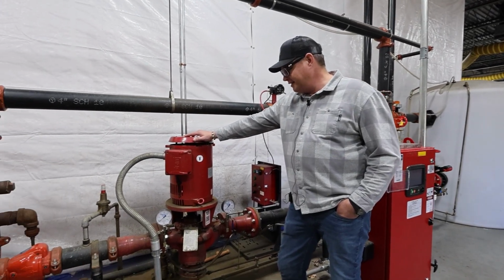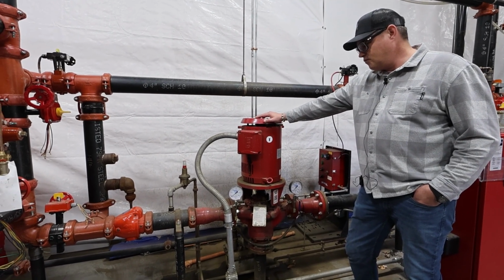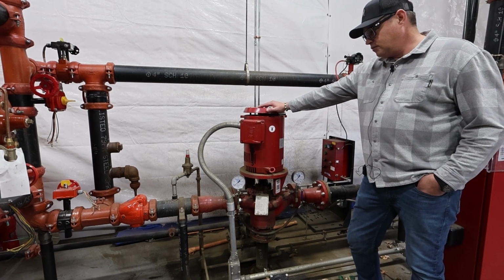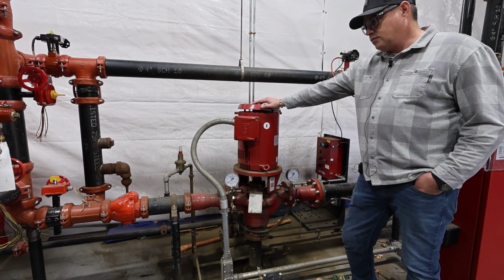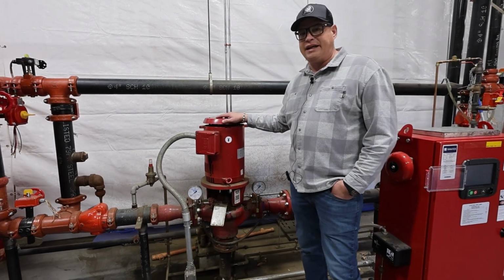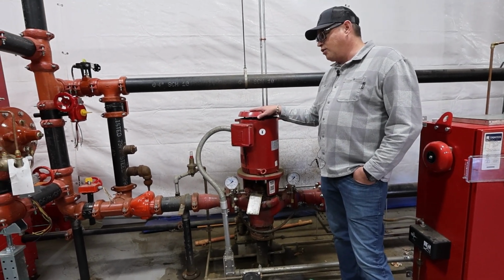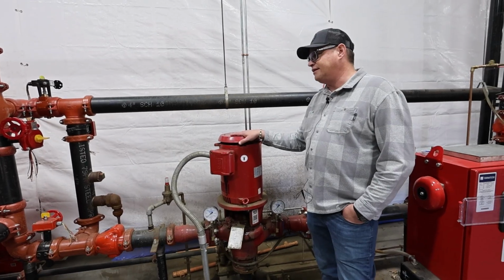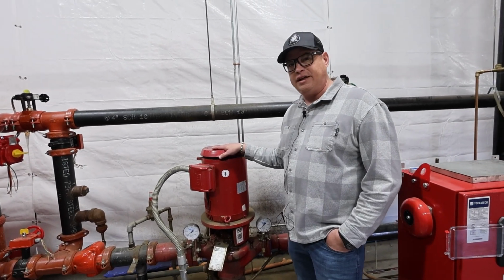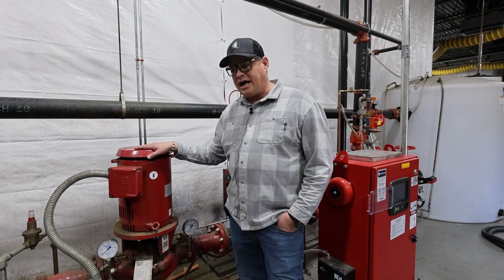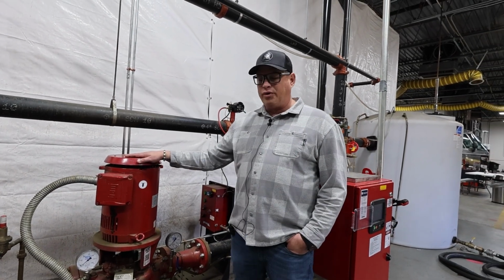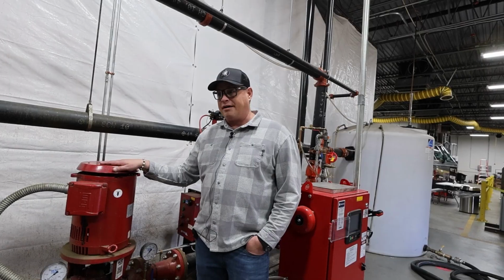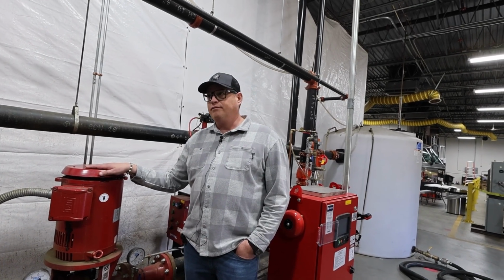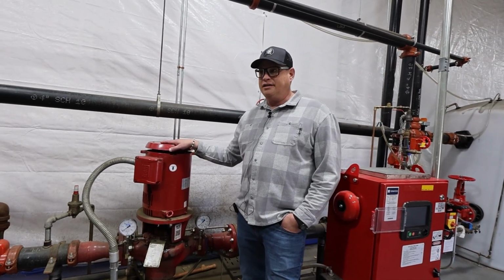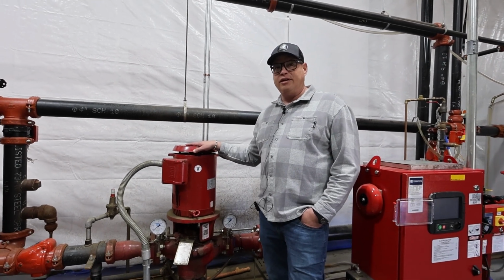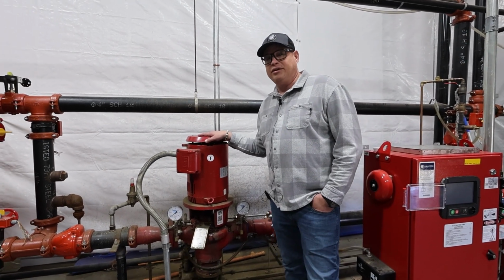Anything else from a general preventative maintenance standpoint? How do I make sure these pumps run for 20, 30 years? Just take care of them. If you take care of the pump, it'll take care of you when you need it. You want to make sure you're leaving the room better than you received it, constantly looking at ways to improve the setup you have, recommending maintenance when necessary. Customers need to understand that it's the most important equipment in the entire building, you need to take care of it so the people in your building are safe.